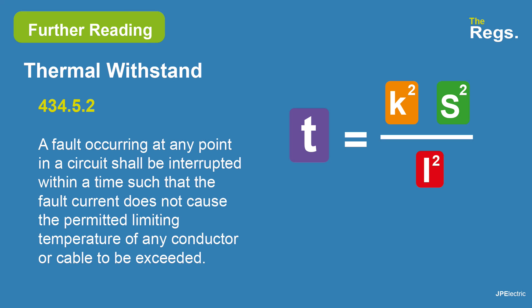So the adiabatic equation gives us the size of the protective conductor that we need. There's also another calculation we need to do: we need to know that the fault is interrupted within a time such that the fault current does not cause the permitted limiting temperature of any conductor or cable to be exceeded — how quickly that cable will get to a limiting temperature. We'll do that equation in another video. I hope that was of some use to you — thanks very much for watching.